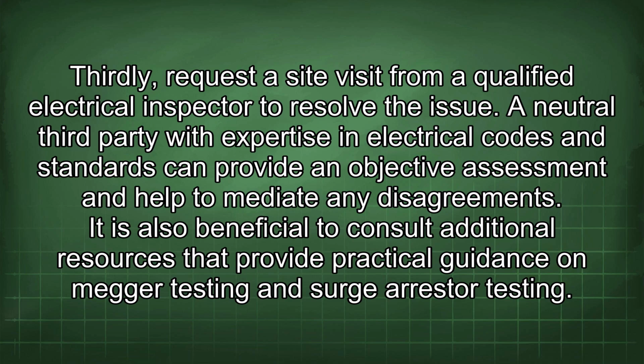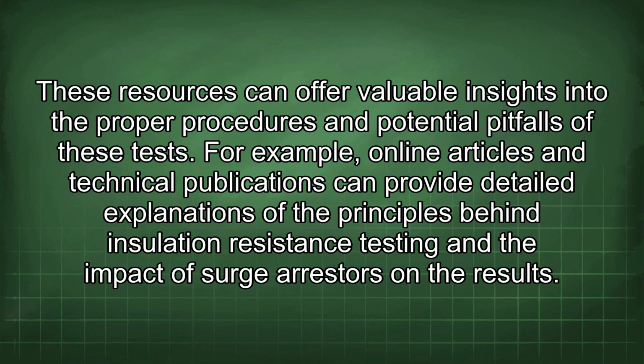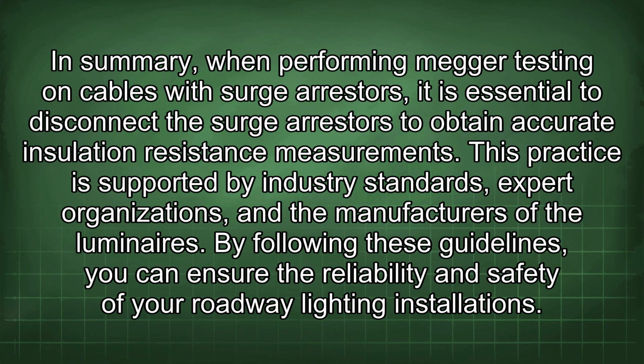A neutral third party with expertise in electrical codes and standards can provide an objective assessment and help to mediate any disagreements. It is also beneficial to consult additional resources that provide practical guidance on Megger testing and surge arrestor testing. These resources can offer valuable insights into the proper procedures and potential pitfalls of these tests. For example, online articles and technical publications can provide detailed explanations of the principles behind insulation resistance testing and the impact of surge arrestors on the results. In summary, when performing Megger testing on cables with surge arrestors, it is essential to disconnect the surge arrestors to obtain accurate insulation resistance measurements. This practice is supported by industry standards, expert organizations, and the manufacturers of the luminaires. By following these guidelines, you can ensure the reliability and safety of your roadway lighting installations.